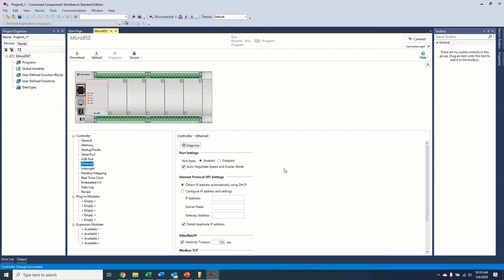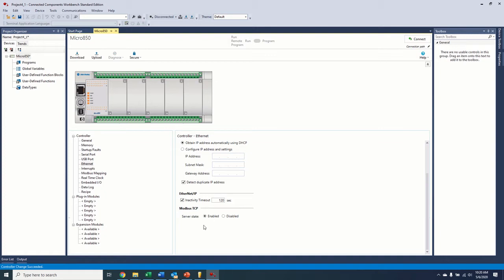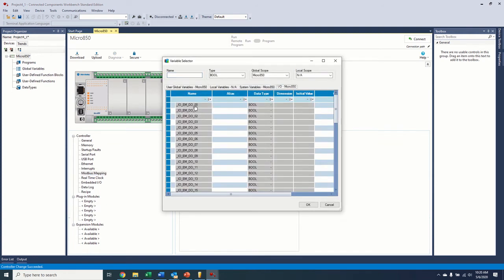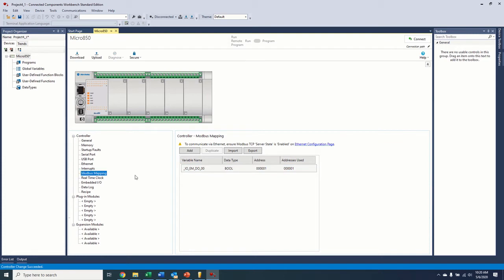The Ethernet port, again, pretty self-explanatory. You can assign the Ethernet settings just like you would with any other Rockwell controller. The only thing that's different is down here at the bottom, just like with the MicroLogix 1400, these controllers are capable of Modbus TCP. So if you would like to enable that, you can do that down here, and then over here on the left, you can see that there's a Modbus mapping. So from here, if you wanted to map, say, an embedded digital out to a Modbus address, it's just that easy. So now, out of that Modbus or out of that Ethernet port, this would allow this mapping on the Modbus network. It's pretty easy.